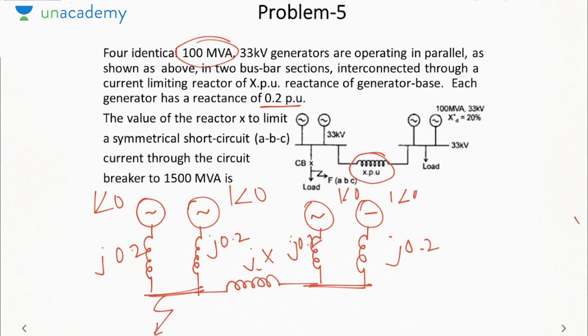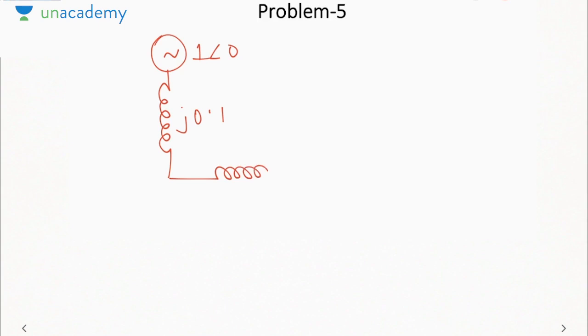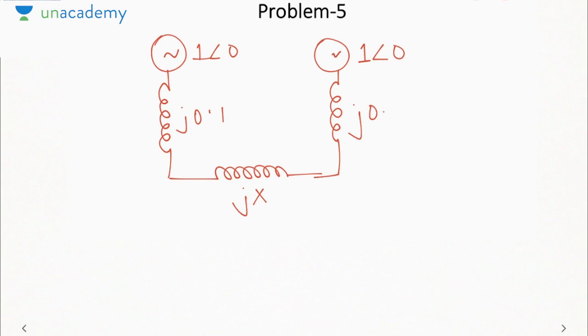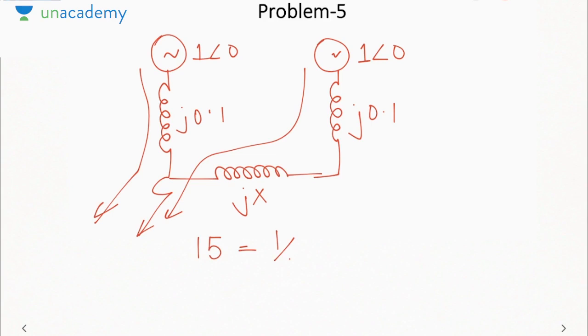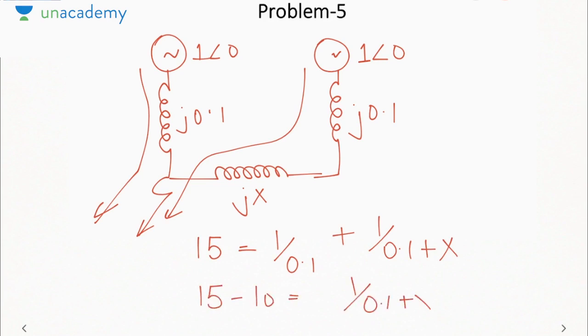The fault is occurring here. So how will this be reduced? This will be 1 angle 0 in series with parallel combination of the two, that is J.1 in between a reactor X and then the other generator, that is 1 angle 0 in series with J.1. Now fault is occurring here, so one current will go directly, other will flow like this. So 15 will be equal to 1 by 0.1 plus 1 by 0.1 plus x. 15 minus 1 by 0.1 will be 10. So it implies x will come out to be 0.1 pu.